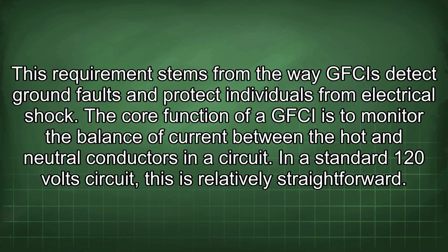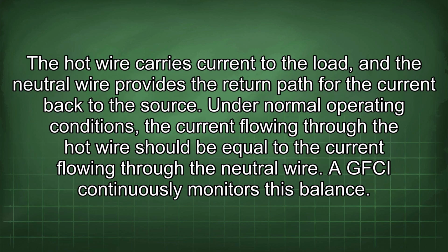The core function of a GFCI is to monitor the balance of current between the hot and neutral conductors in a circuit. In a standard 120-volt circuit, this is relatively straightforward. The hot wire carries current to the load, and the neutral wire provides the return path for the current back to the source. Under normal operating conditions, the current flowing through the hot wire should be equal to the current flowing through the neutral wire.